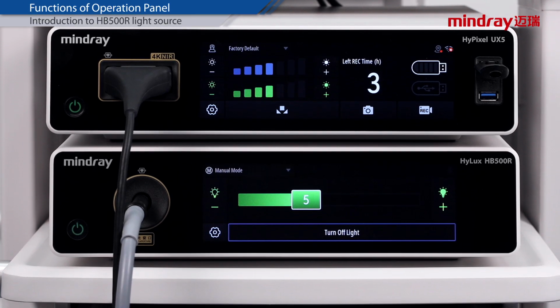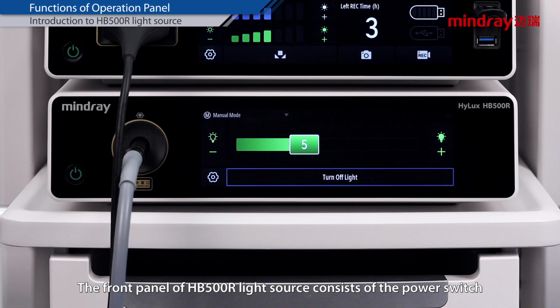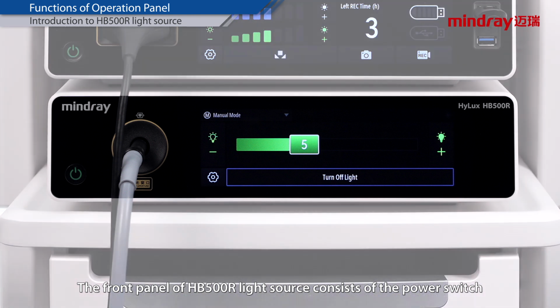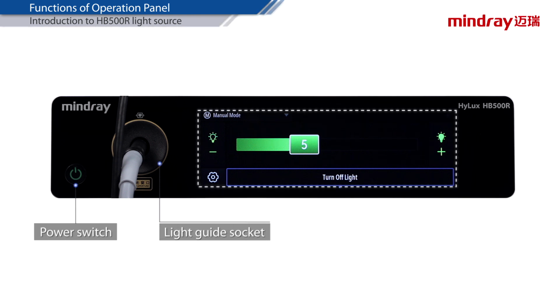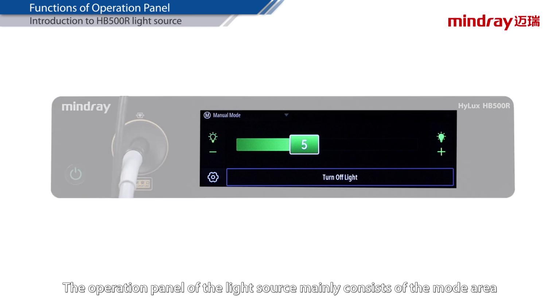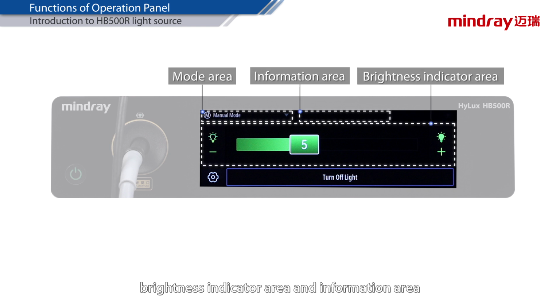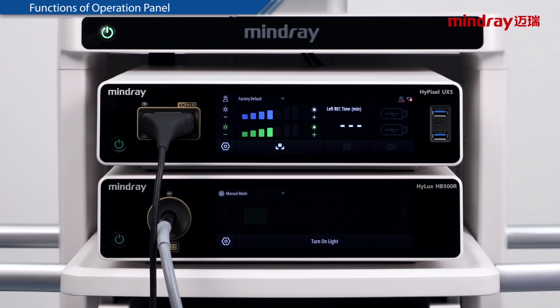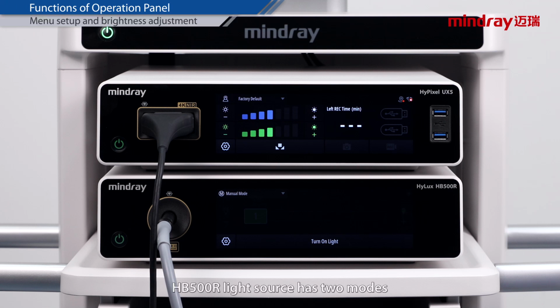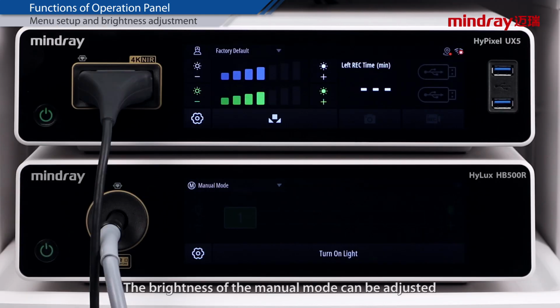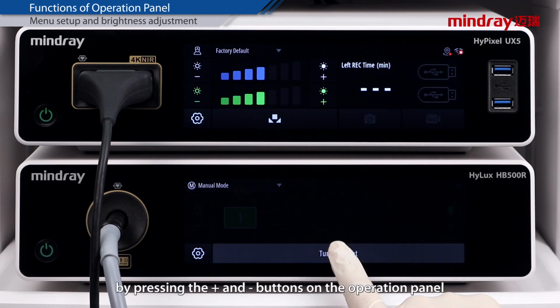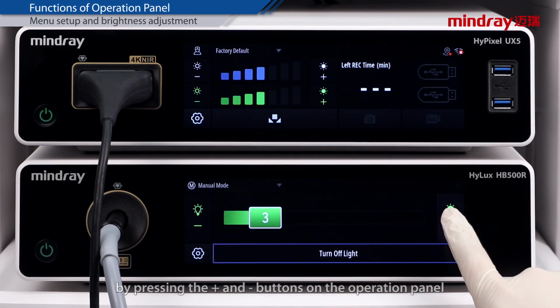Introduction to HB500R light source. The front panel of the HB500R light source consists of the power switch, light guide socket, and touchscreen. The operation panel of the light source mainly consists of the mode area, brightness indicator area, and information area. Menu setup and brightness adjustment. HB500R light source has 2 modes, manual and auto. Click the mode area and a drop-down menu will be displayed. Select the desired mode. The brightness of the manual mode can be adjusted by pressing the plus and minus buttons on the operation panel.